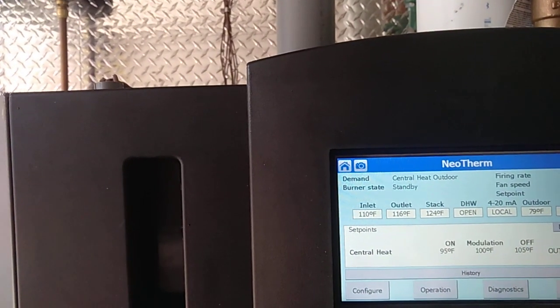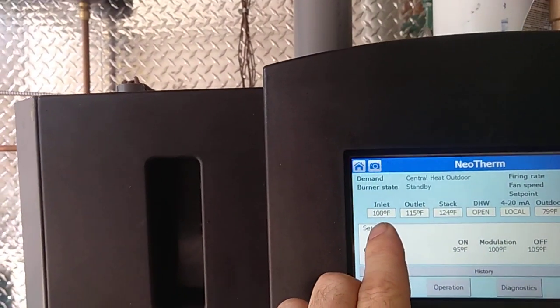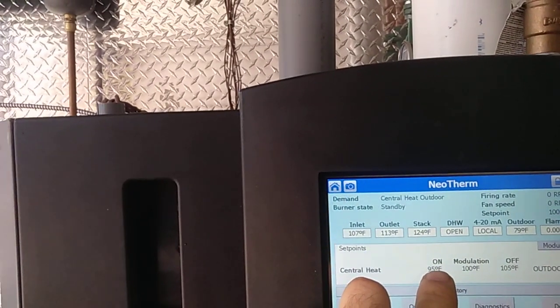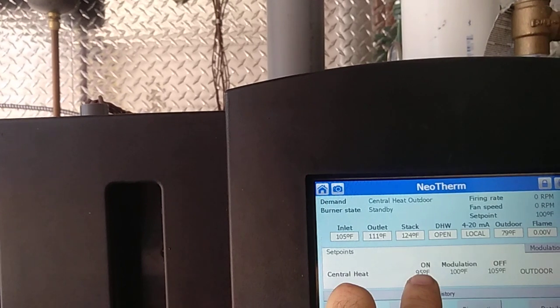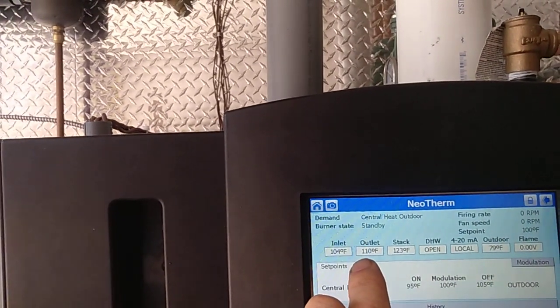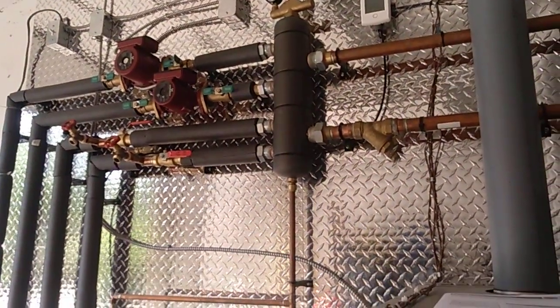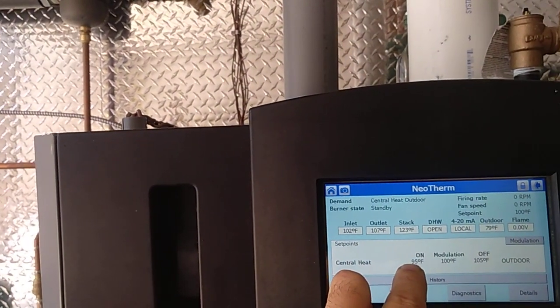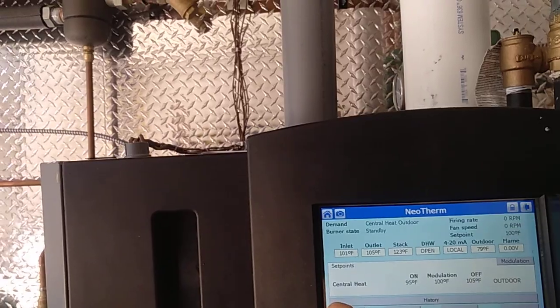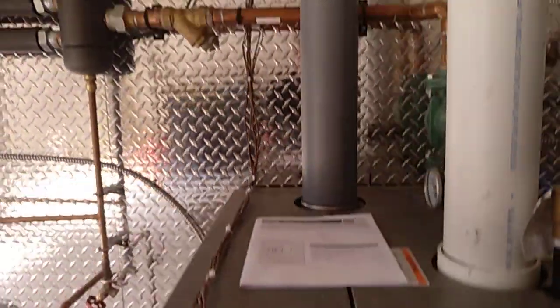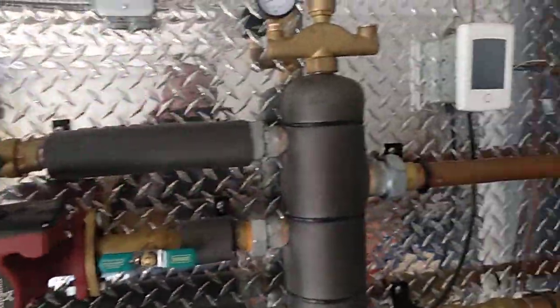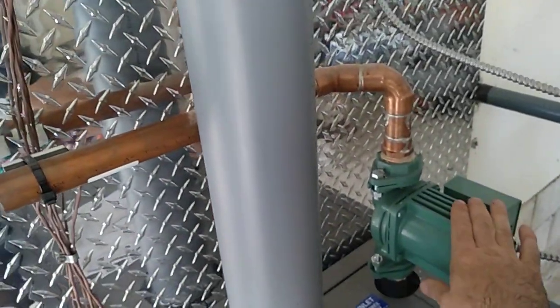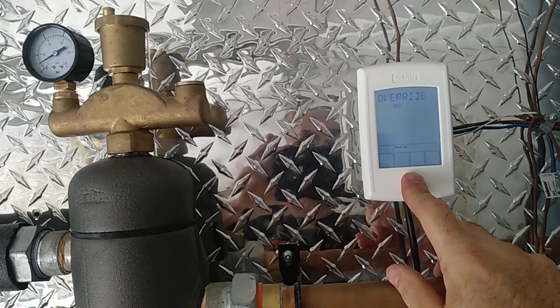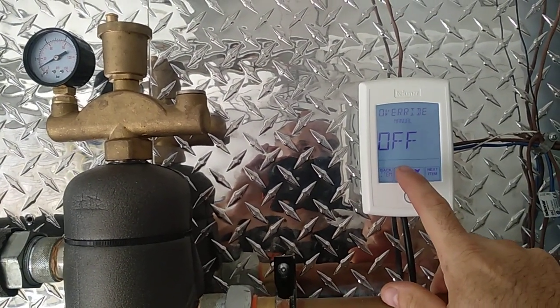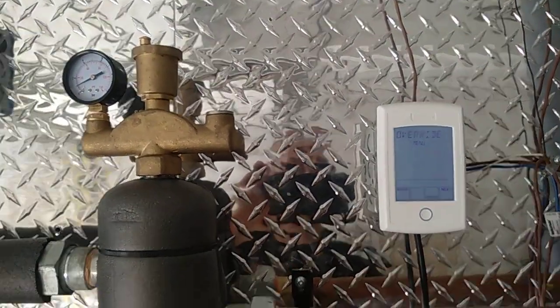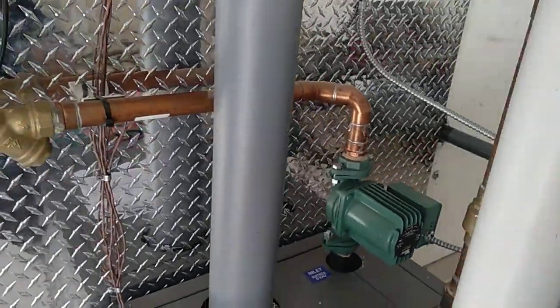Right now it's not firing because the set point on this boiler is calling for it to turn on when the outlet is 95 Fahrenheit. Right now the outlet is 111, so it's just circulating the water already in the boiler and in the hydraulic separator and in the loops, which are much warmer than the set point. So right now this system will not start on. Well, you can hardly blame it in plus 30 degrees. But the pumps are all circulating, the control is working, main pump is circulating, everything is running fine. So we can just turn this override off. The boiler pump will circulate for an additional 5 minutes because that's what it's set to.